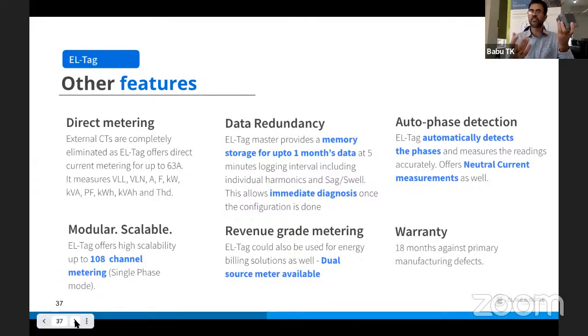In a normal scenario, you will have multiple meters placed at different places, and you would do wiring all the way from the first panel to the second panel to the last panel, etc. Here it's not like that. You have a meter and several of them within the panel itself connected, and through either Wi-Fi, Ethernet, or 485, it just communicates. So reliability is very good. Since this is connected within this, the data of EL-Tag is also stored inside the power quality meter.